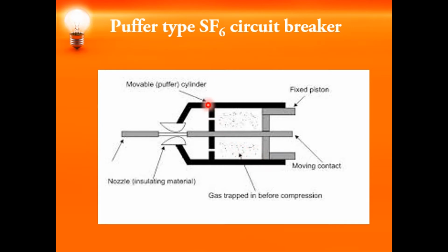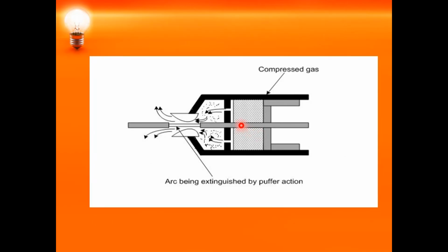This is the movable cylinder. Whenever a fault occurs, the contacts get separated, and when the arc is formed, the gas will remove all the ionized particles. You can observe here that when the contacts get separated, the SF6 gas flows out and removes all the ionized particles through the nozzle. That is how this SF6 gas works. The piston moves forward so that the SF6 gas moves out of the vent, flows axially, and removes all the ionized particles. This is how the SF6 circuit breaker works.